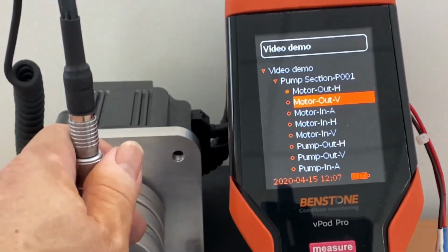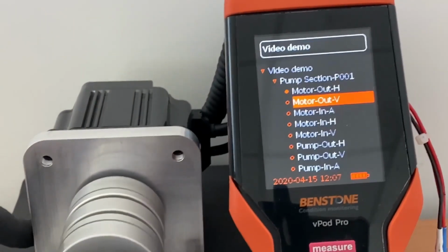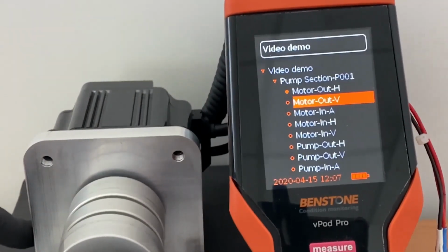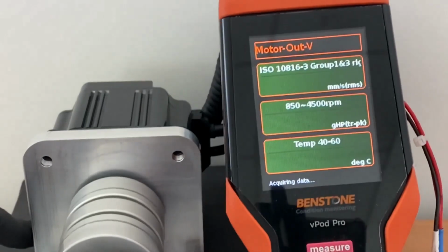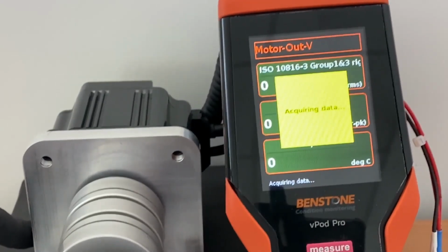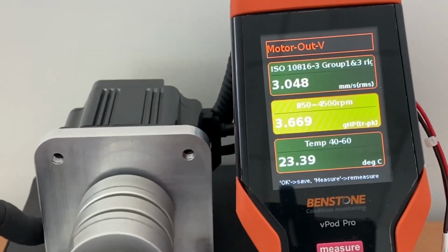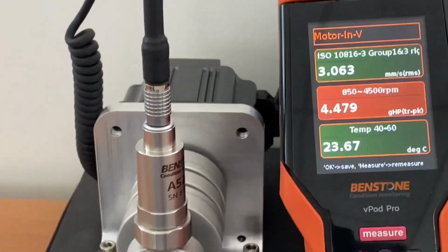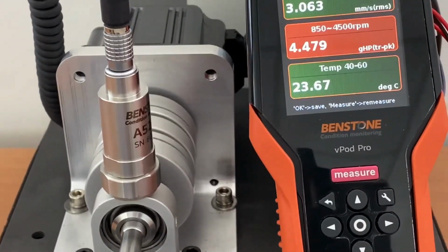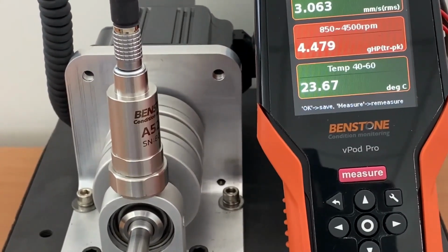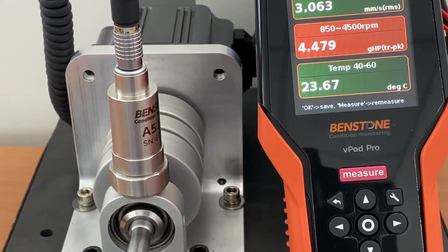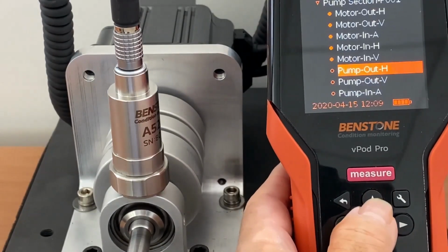Next, we will look at by moving the accelerometer to the second point, motor out-V, and then press the measure once again. Once completed, we will press the OK button to save the file, or save the data. If you notice, in this demonstration, we have installed a bad bearing to show how the measurements can be seen more clearly. As you can see, the bearing's true peak value is very high and is over the alarm levels.